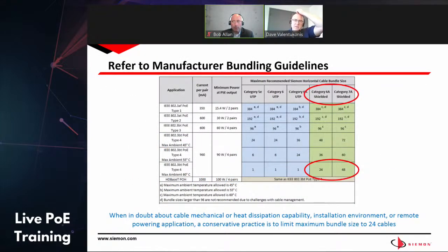So this here is a manufacturer guideline. This happens to be Siemon, but a lot of manufacturers may have it. It talks about the maximum bundle size for different media types as you go from the top of the screen, which is type 1 PoE, all the way down to type 4 PoE operating at that 60-degree limit that we talked about, so actually getting up to 75 degrees C overall with the heat rise. And as you can see, for category 6A shielded and category 7A, that magical number of 24 applies. Keeping those 24 cable bundles makes a lot of sense.